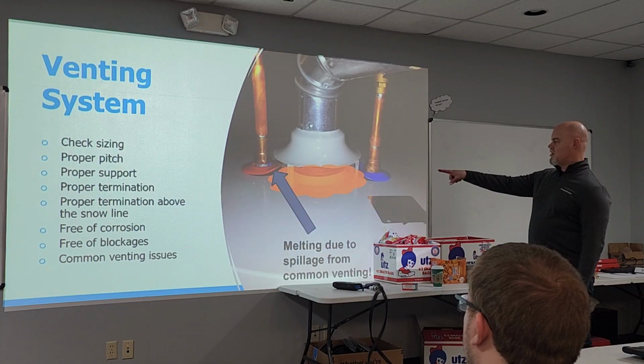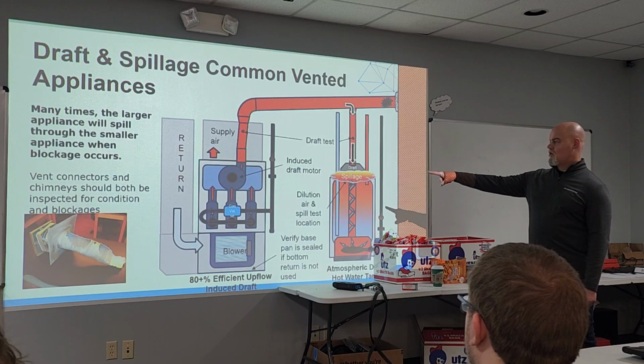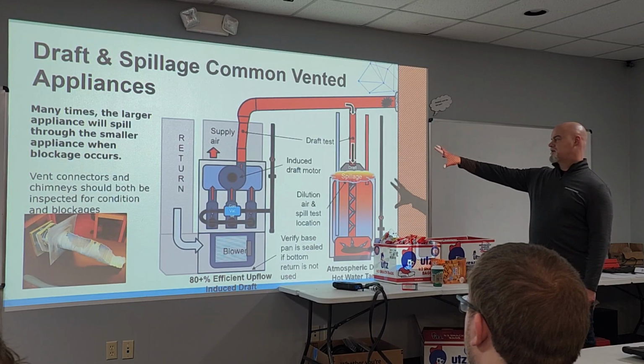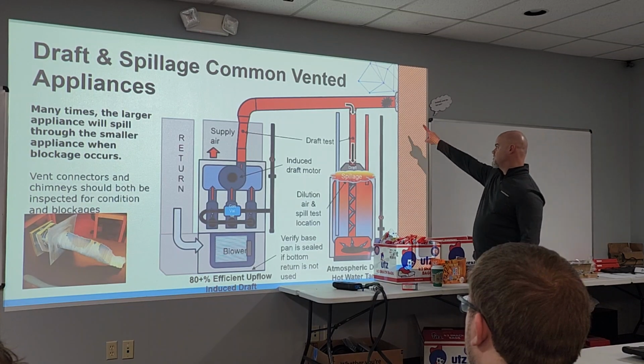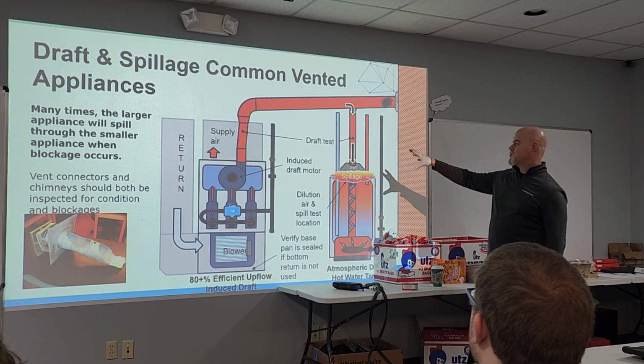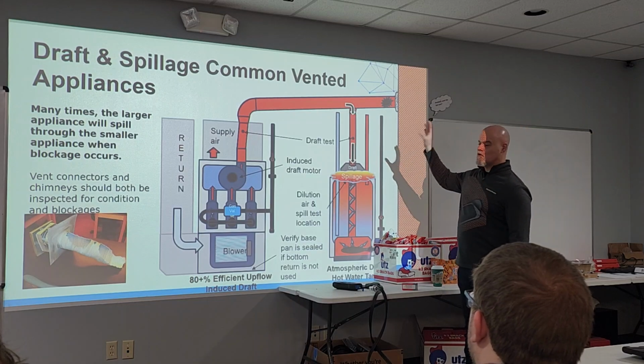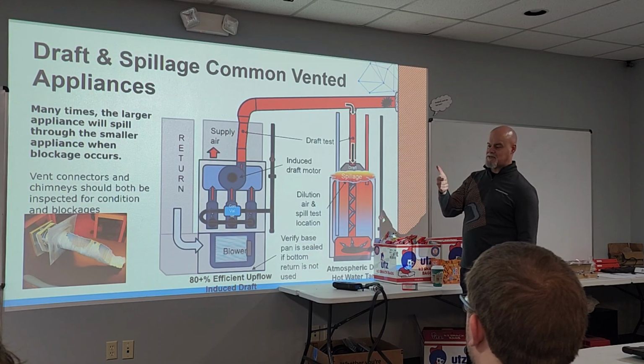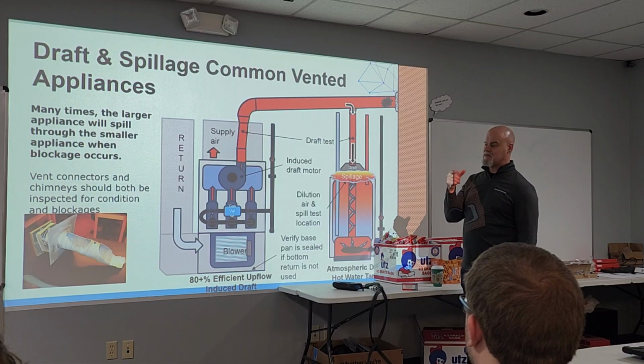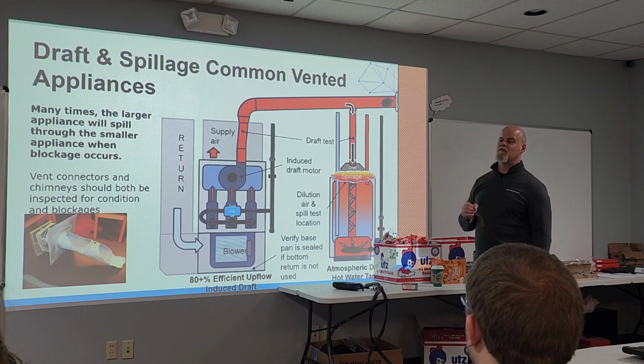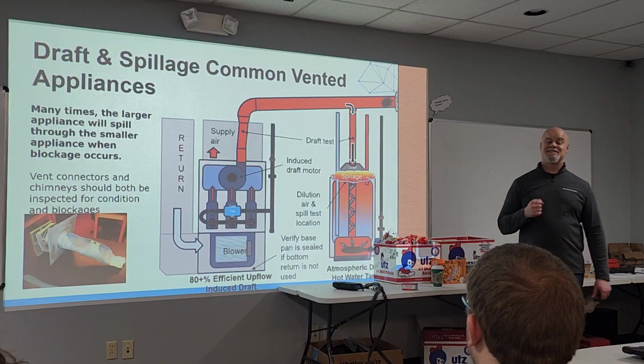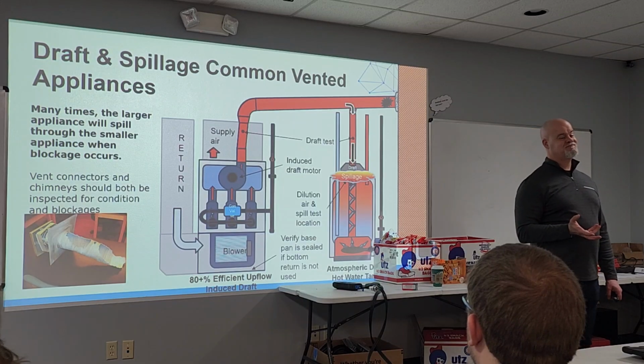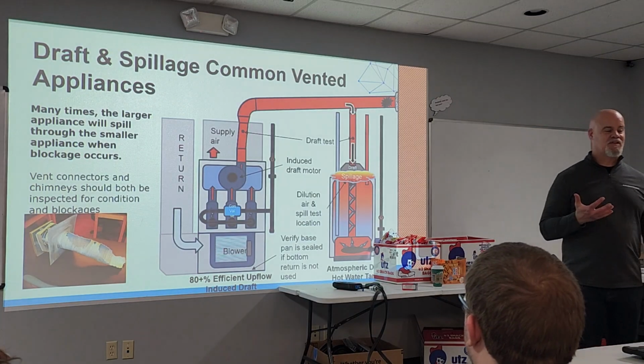So you see it here, these grommets, see the spillage here? Over here, the larger appliance is going to spill into the smaller one just because of the physics when there's a blockage. You see the blockage here. So we want to make sure we check the integrity of our draft every time, obviously when installing, but also every maintenance or diagnostic visit, to verify that our system isn't, essentially, constipated. Because your system is a living and breathing thing.